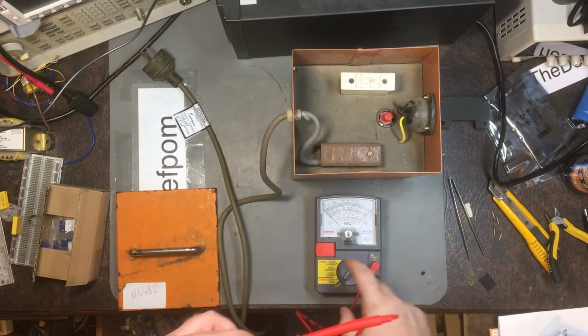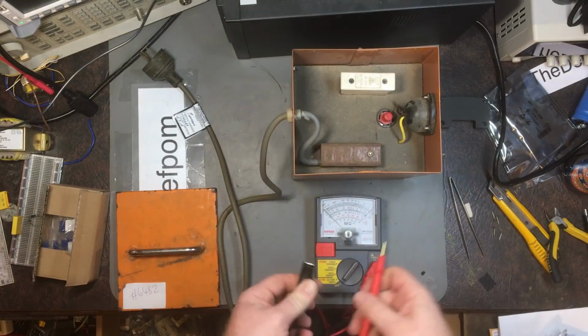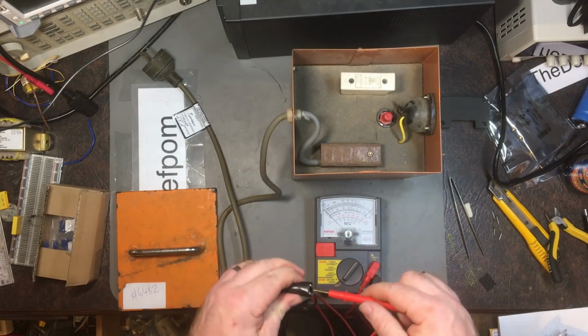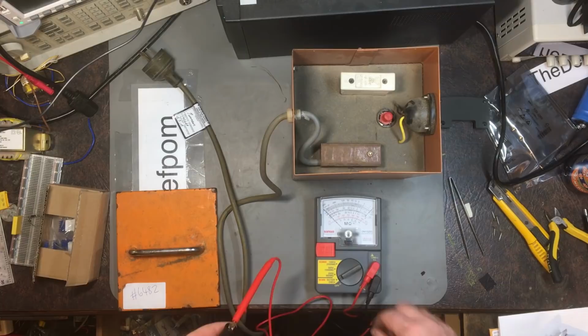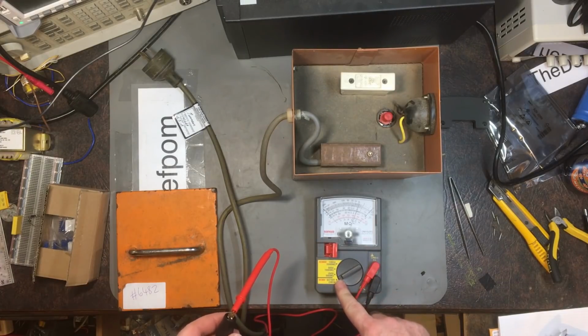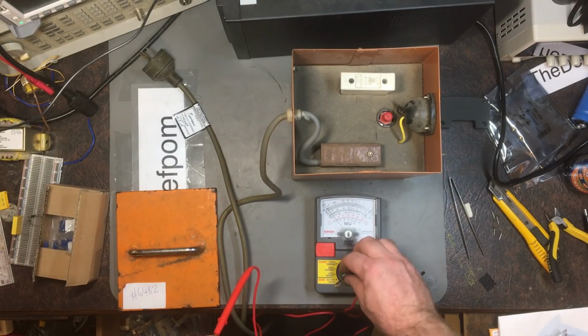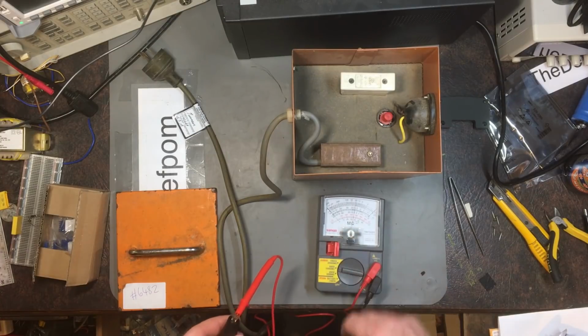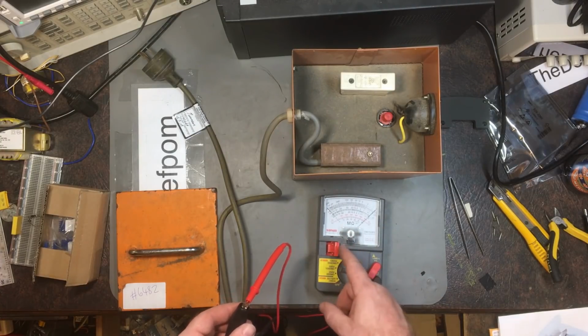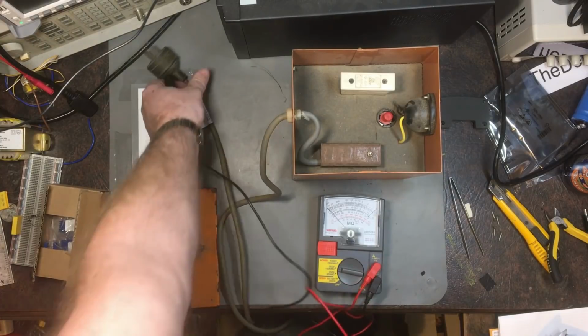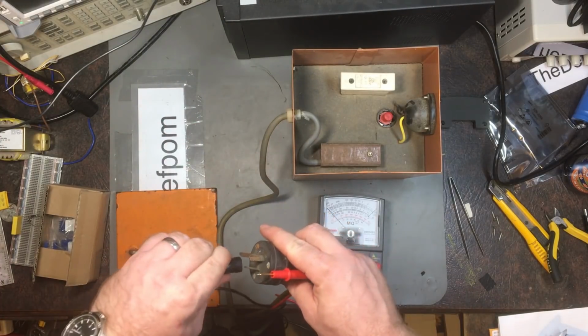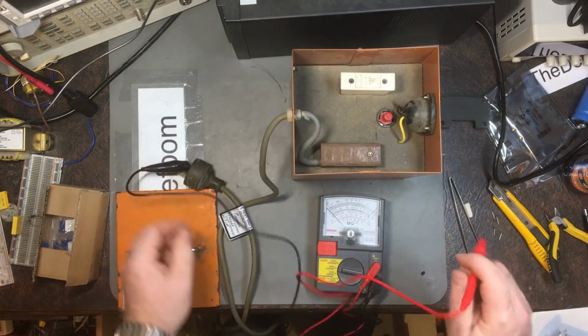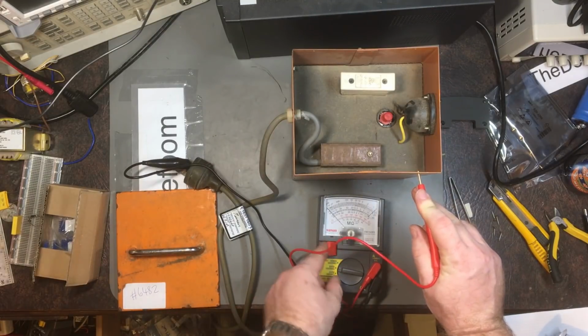Okay, so I've got my Sanwa insulation resistance tester out, let's do some checks on this. Battery check - yep, cool, should be fine, it's got a brand new battery in it. Let's do a resistance check - 500 volts is what I want. That's fine, so let's see how we go between one of them, and we'll check the casing first.